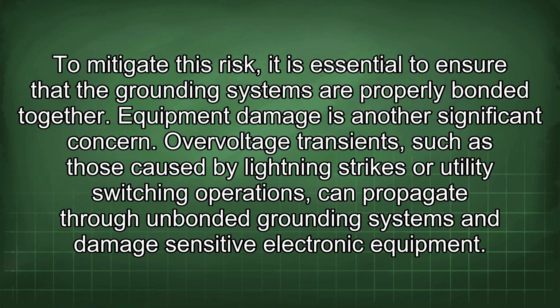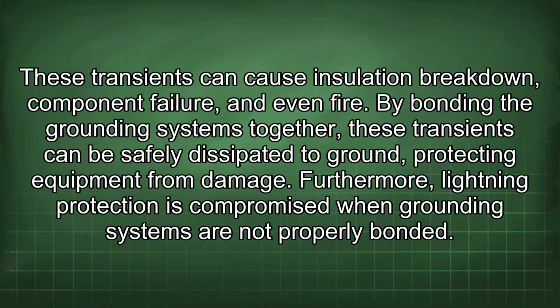Equipment damage is another significant concern. Overvoltage transients, such as those caused by lightning strikes or utility switching operations, can propagate through unbonded grounding systems and damage sensitive electronic equipment. These transients can cause insulation breakdown, component failure, and even fire. By bonding the grounding systems together, these transients can be safely dissipated to ground, protecting equipment from damage. Furthermore, lightning protection is compromised when grounding systems are not properly bonded.